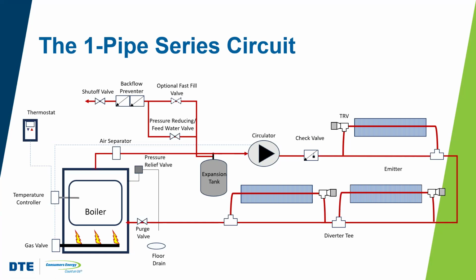The downside to this is you still have that water that's flowing through, to a degree, through each emitter, even though the water has an option, right? It can go this way here, or it can go this way here. When it comes back to this point and gets mixed here, right? It's going to be a mix of this temperature that was at this point and the temperature that it was coming out of this emitter. So this temperature is going to be lower than that temperature. And that's the temperature that's coming around here to this next emitter, right? So you still have that issue.